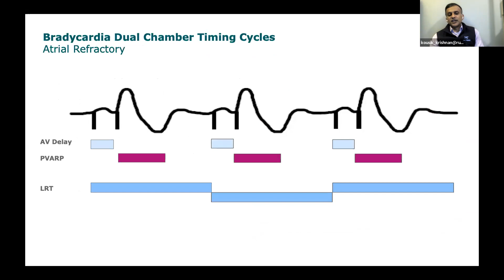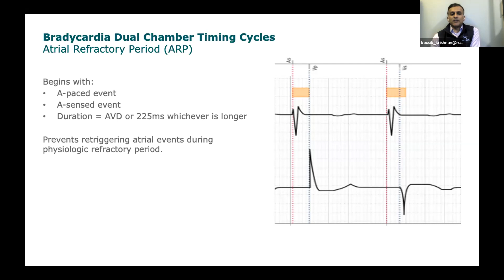So again, we have an AV delay, a PVARP, a lower rate timer. There's an atrial refractory period as well after an A-paced or an A-sensed event. This is to prevent re-triggering of other atrial events during a refractory period, if there are extraneous signals, or if you don't want anything to happen in the atrium right after you've paced. So there's a defined atrial refractory period as well.